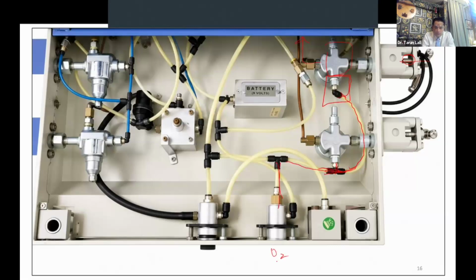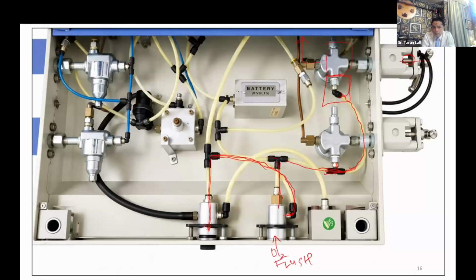This is the oxygen flush. As you all know, the oxygen flush is connected directly to the intermediate pressure system. And from the oxygen flush, when I press it here, where does this outlet go? One of the connections from the oxygen flush goes directly to your common gas outlet. This is what I wanted to show you. So when I press the oxygen flush, you will see that its output is going directly to the circuit, to the common gas outlet, which means that when you press the oxygen flush, the patient gets oxygen at high flows at 40 to 60 psi pressure, which is enough to cause barotrauma. So that is why we never use it when the patient is connected.